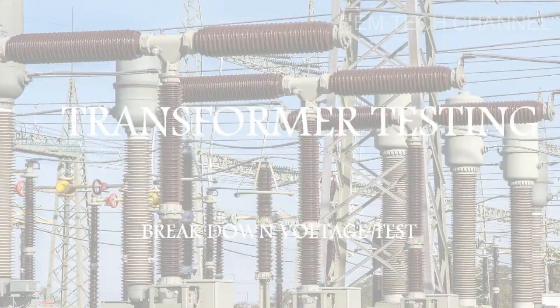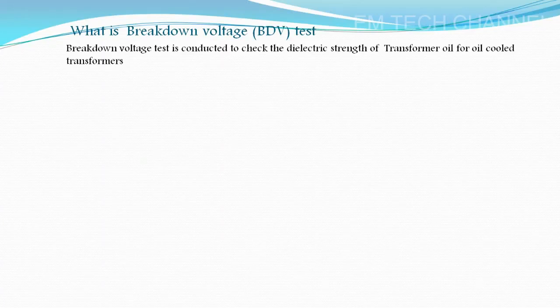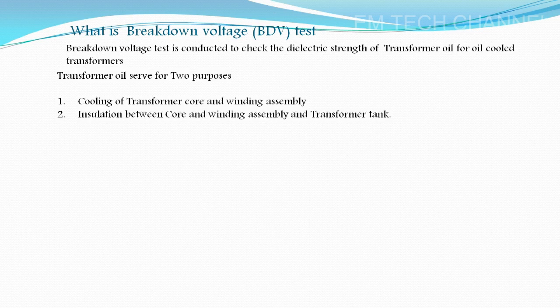Let's start the video. The breakdown voltage test is conducted to check the dielectric strength of the transformer oil for oil cooled transformers and instrument transformers such as current transformers and potential transformers, and for oil filled on-load tap changers and oil filled circuit breakers. Transformer oil serves two purposes. One is cooling the core and winding assembly in the transformer, and second, it acts as an insulator between the transformer tank and the core and winding assembly.